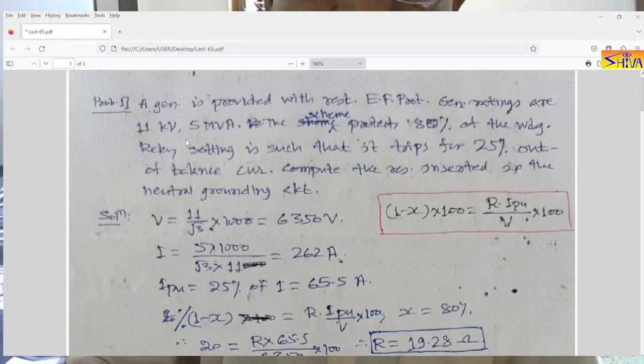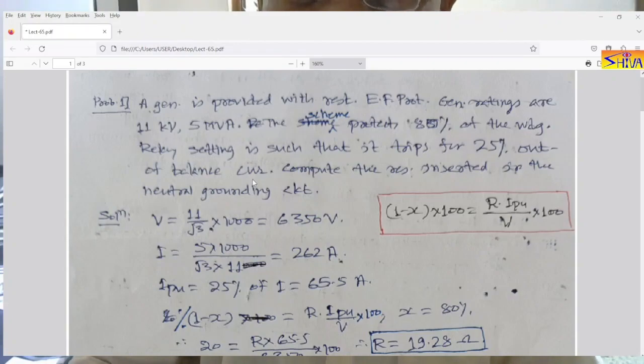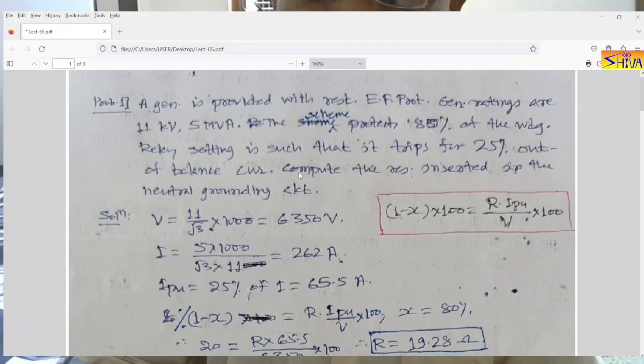First numerical: a generator is provided with restricted earth fault protection. Generator ratings are 11 kV, 5 MVA. The scheme protects 80% of the winding. The relay setting is such that it trips for 25% out-of-balance current — that is, 25% of the rated current. Compute the resistance inserted in the neutral grounding circuit. This is the formula to be used.